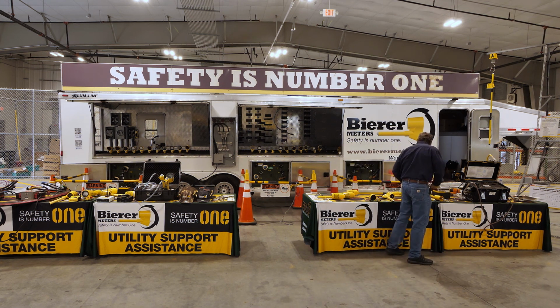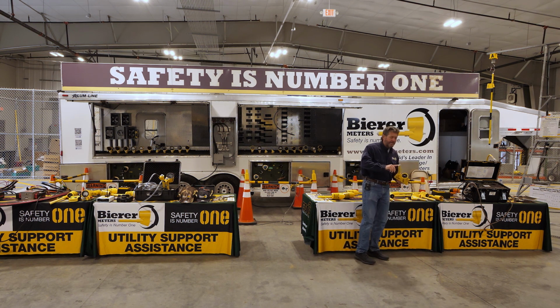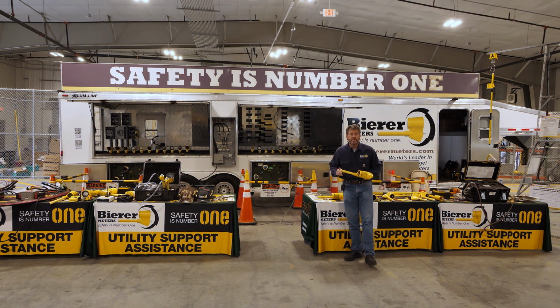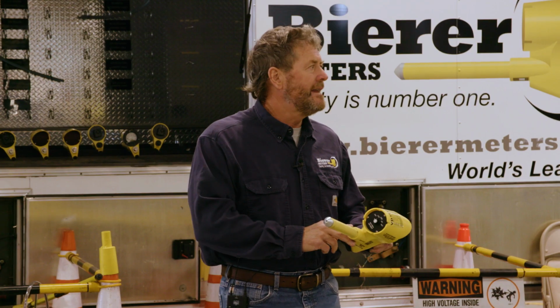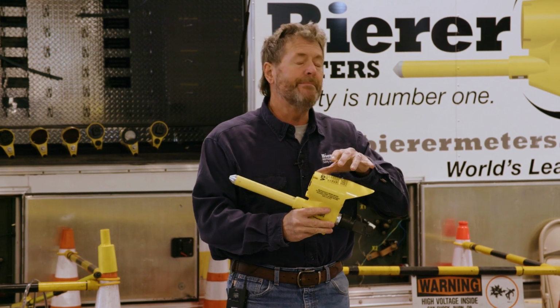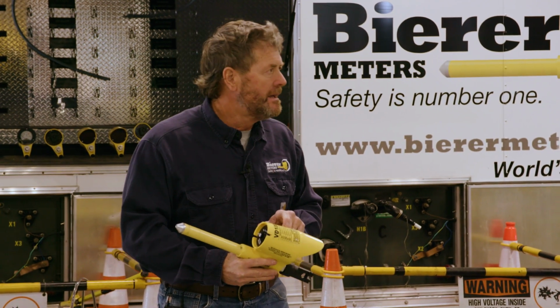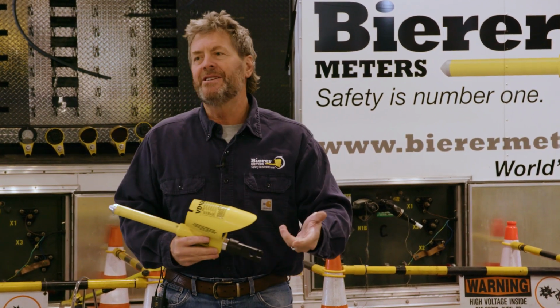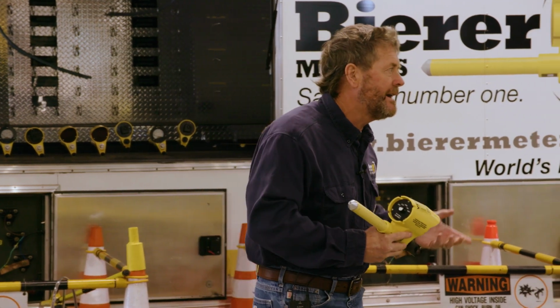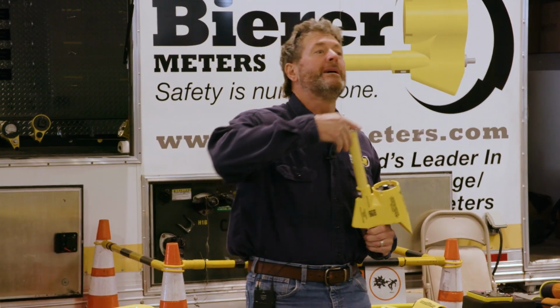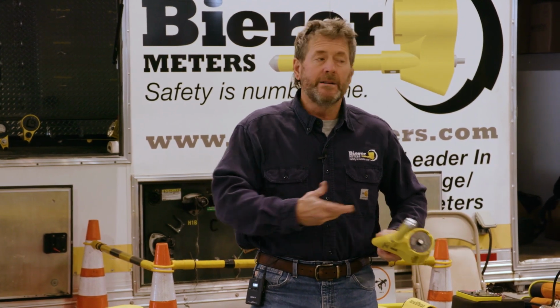Okay, so for care, you want to make sure your probes are clean. Hot stick wipes work great. No markings, no calibration stickers, no grease, no dirt, so that way you alleviate any exterior tracking to the tool, the components. The components that make the tools work, everybody's tools, are conductive. They have to be, right? In order to give you a voltage indication when you're phasing, or phase to ground, or whatever, it must be energized to give you the voltage, right? It has to be energized. Well, it is.